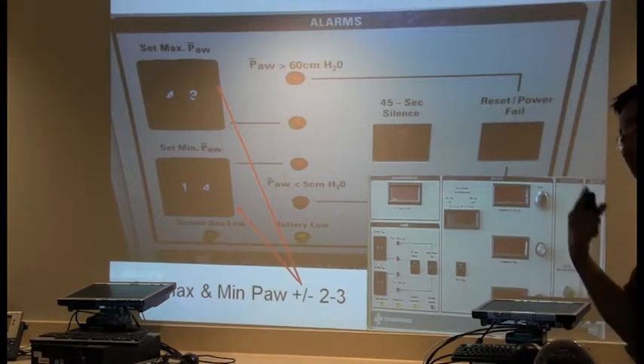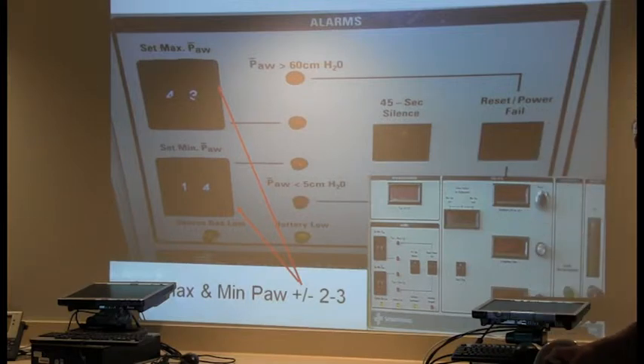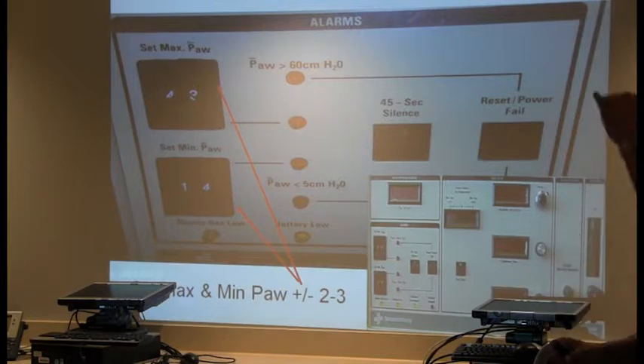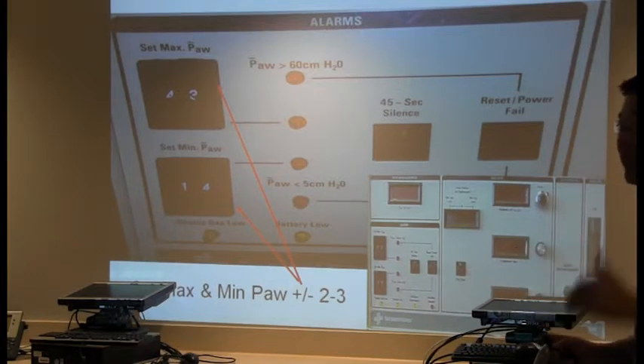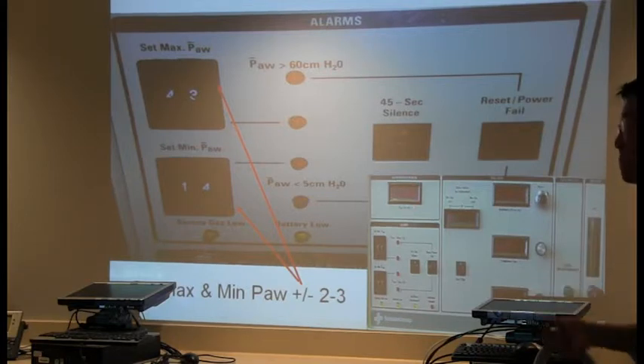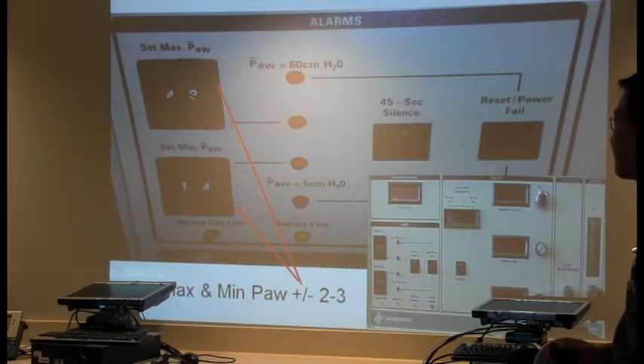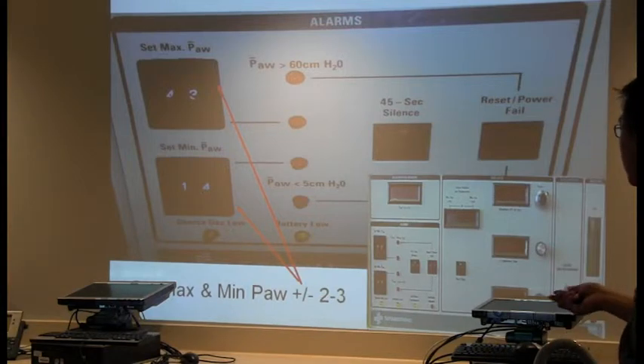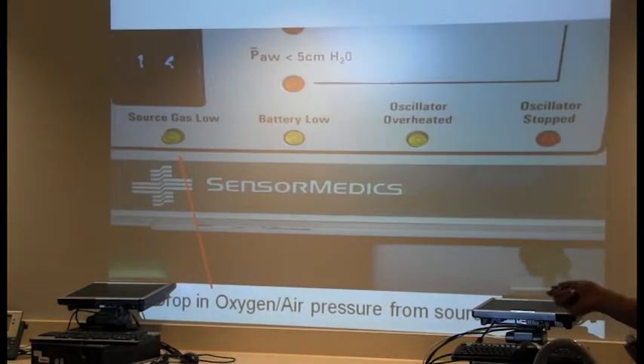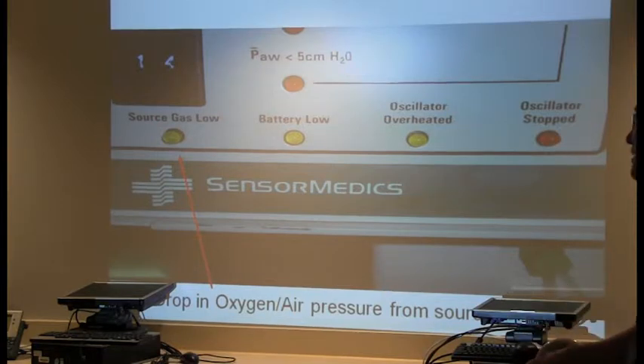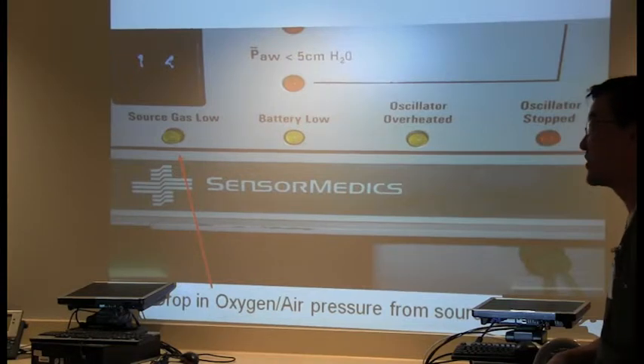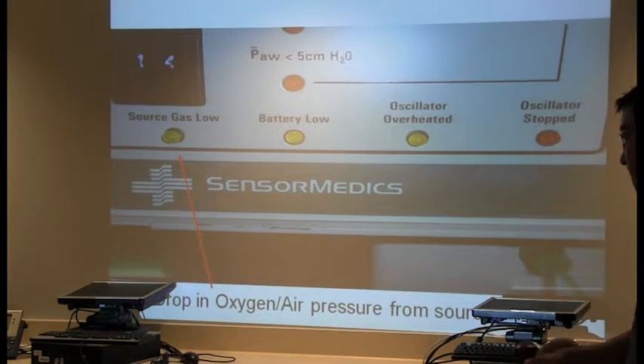If you want to practice, when you get an oscillator, do that. Crank up the alarms and try to start it without the baby on it, and you'll be surprised that nothing will happen. But once you lower that setting to within a reasonable range, 20% of your mean, it pops right up. You're good to go. Now the bottom 4 lights. Source gas low means that you have a drop in oxygen or air pressure from your source gas, the wall. Oxygen is low or air is low. Hopefully you'll have an O2 alarm, an oxygen flow alarm buzzing, if the pressure drops below 40.